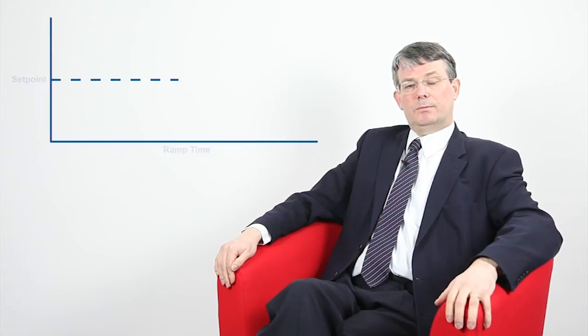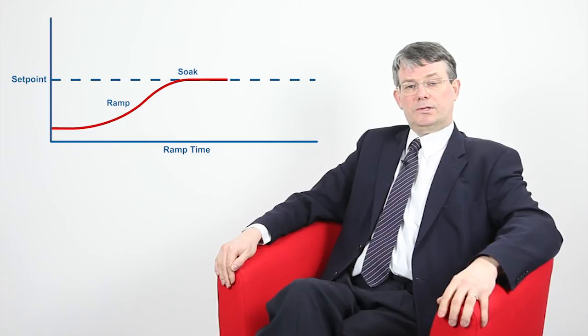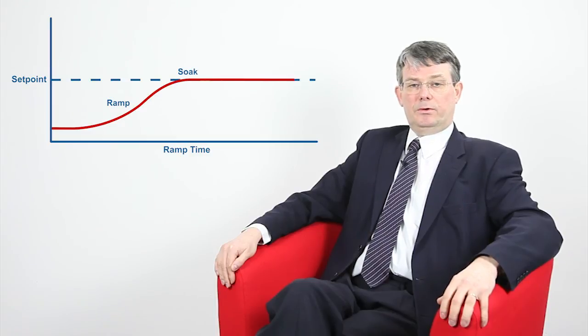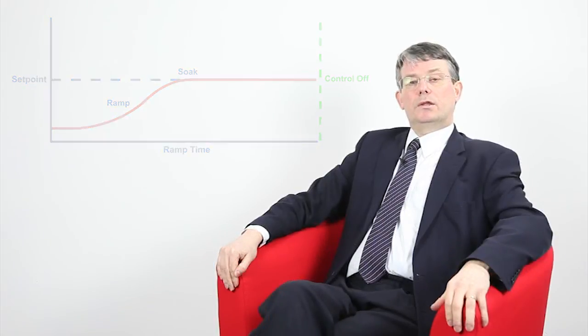Some of our controllers take the ramp soak concept further by adding a soak or dwell at the end of the ramp. Once the ramp is completed, instead of maintaining the final set point value indefinitely, it is held for a defined period of time and then the controller output is turned off, allowing the process to fall naturally. This may be used in a simple heat treating process where a controlled warm-up is required followed by a sustained period at a fixed temperature.